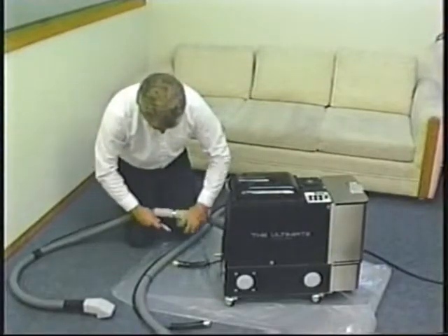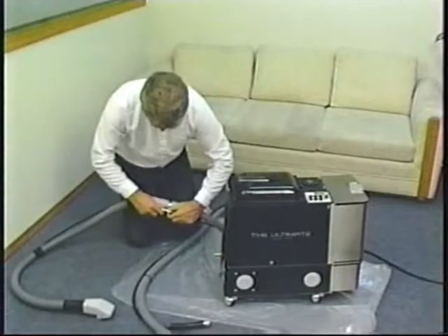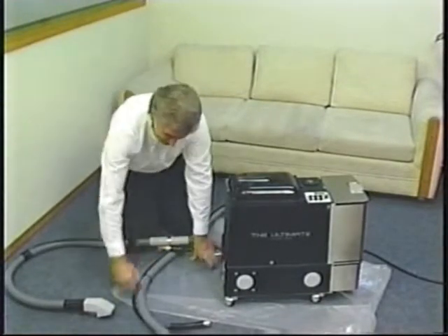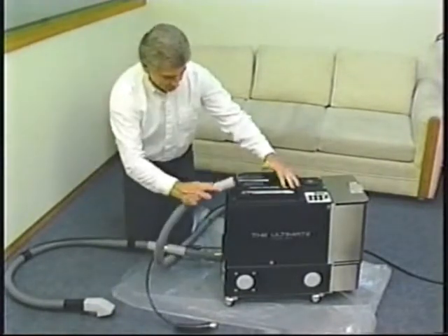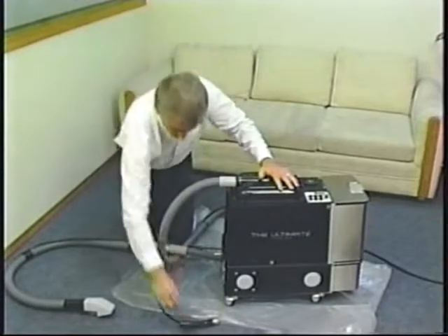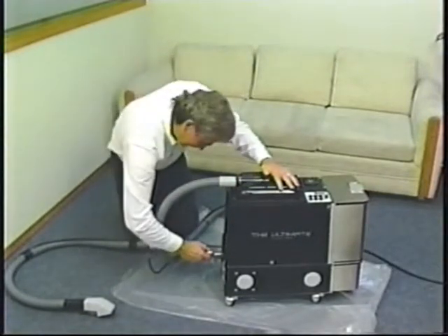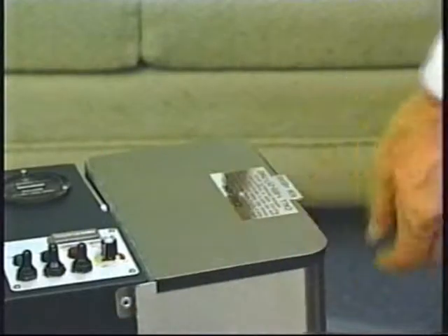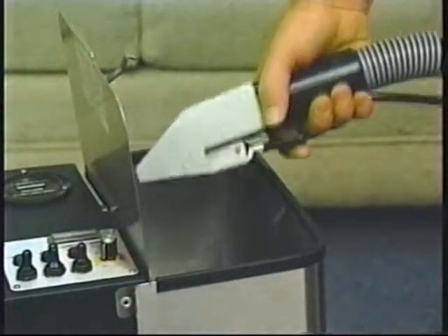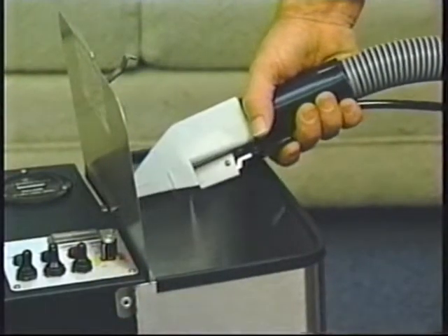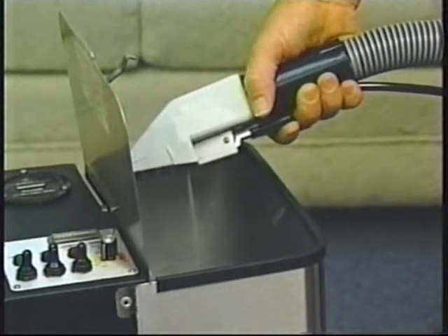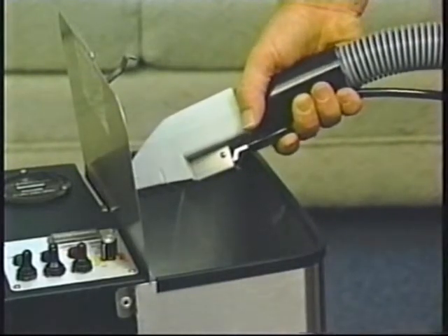Okay, we have cleaning solution in the tank, and we're ready to continue setting up the PB3 for our first cleaning job. Hook up your cleaning tool and your vacuum and pressure lines. Now, turn on the pump switch only and spray into the holding tank. This will send solution through the lines and the heat exchanger and self-prime the machine at the same time.